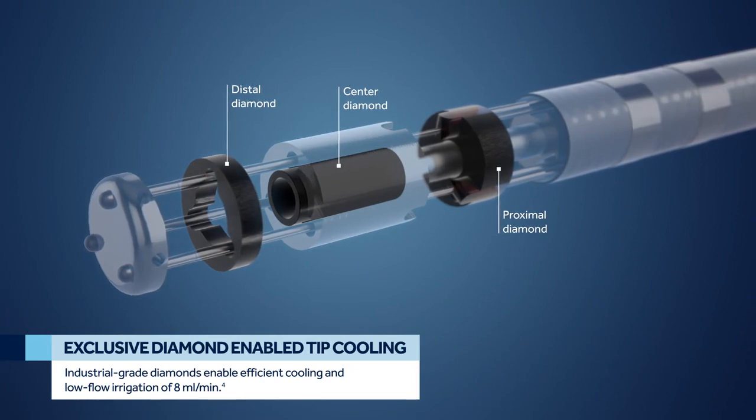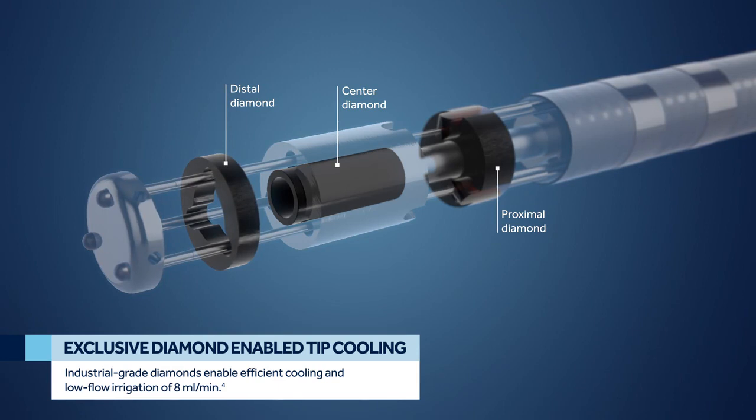The heat diffusivity property of CVD diamonds is 200 to 400 times faster than that of platinum iridium, driving efficient catheter tip cooling and a low irrigation flow rate of 8 milliliters per minute during ablation.